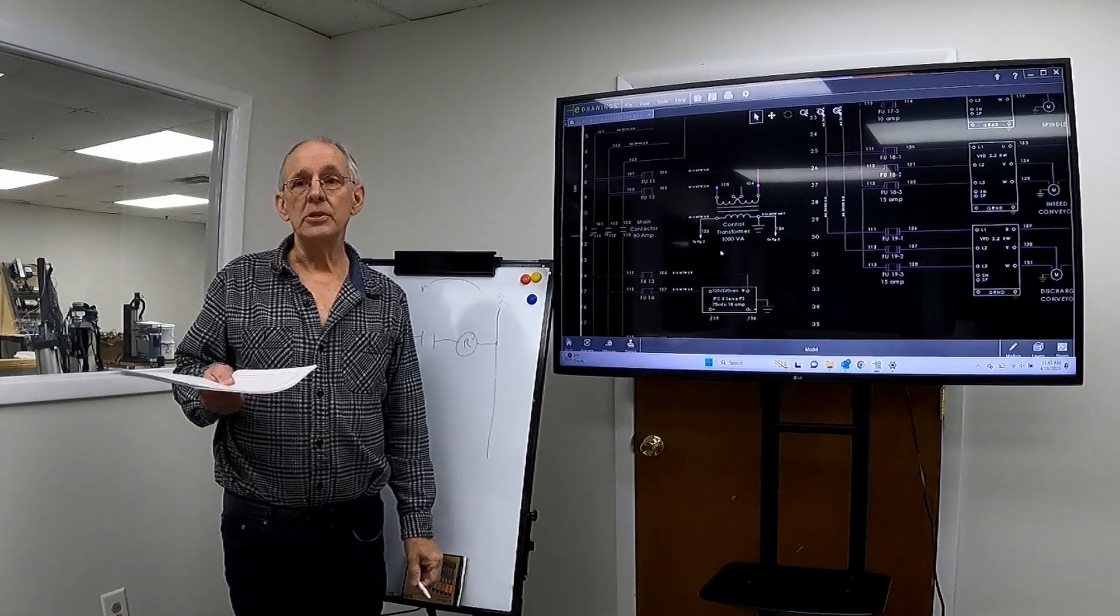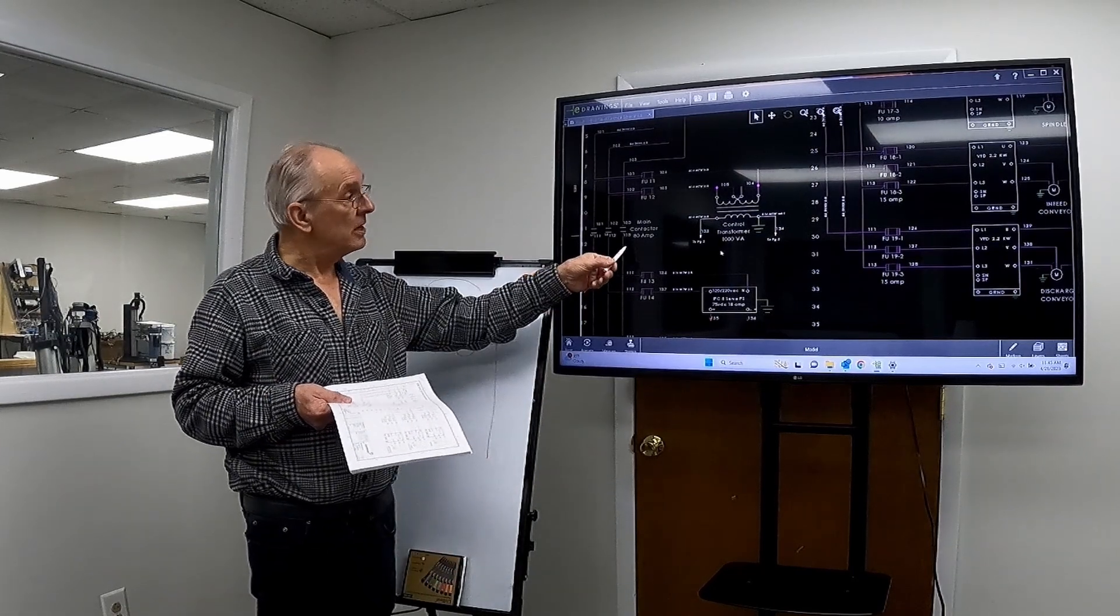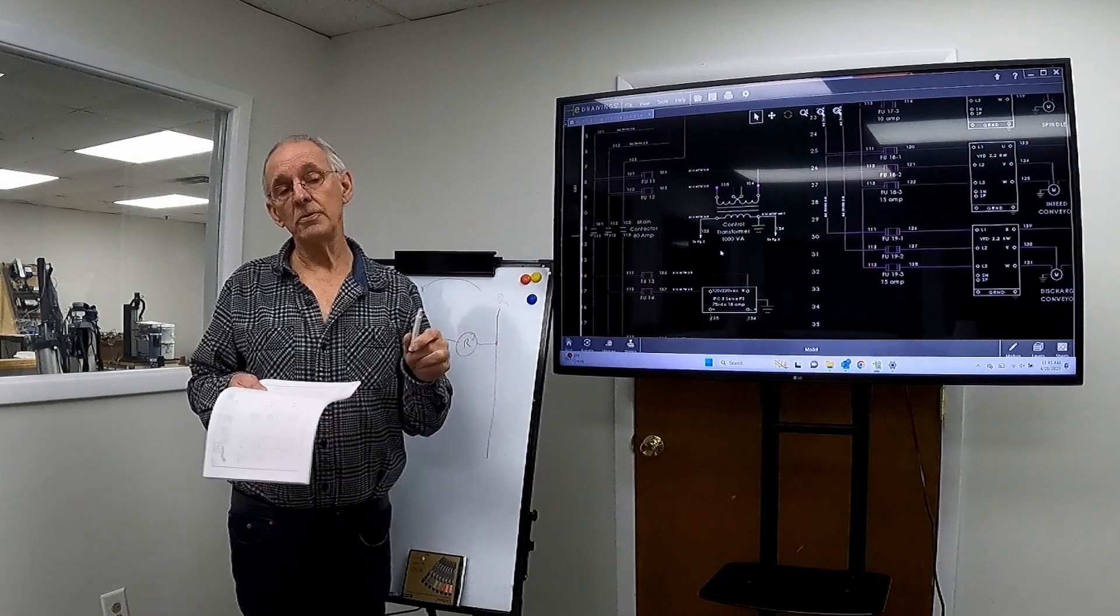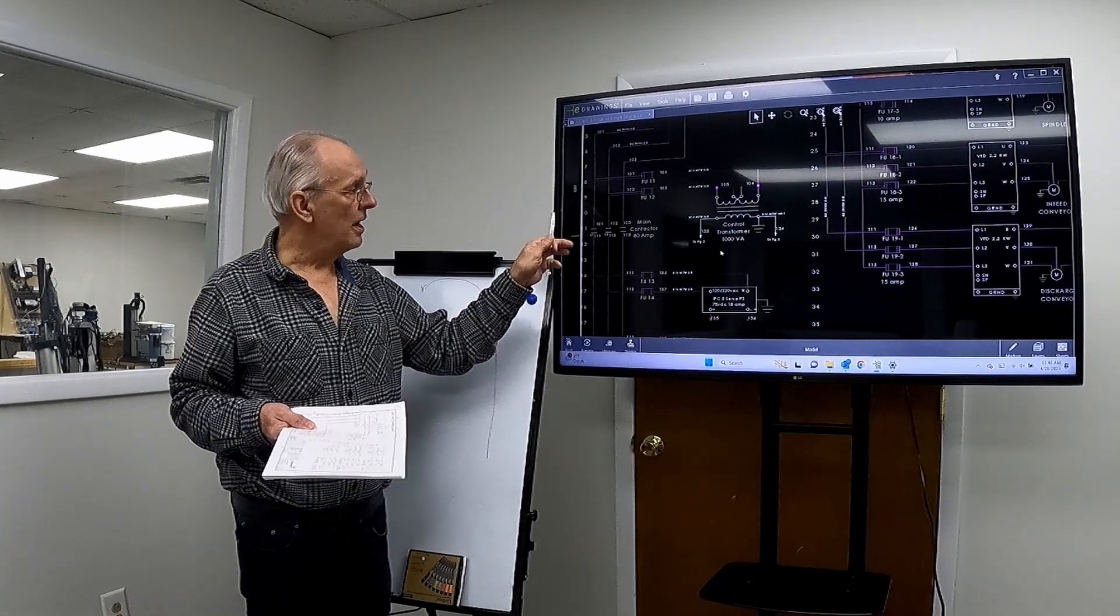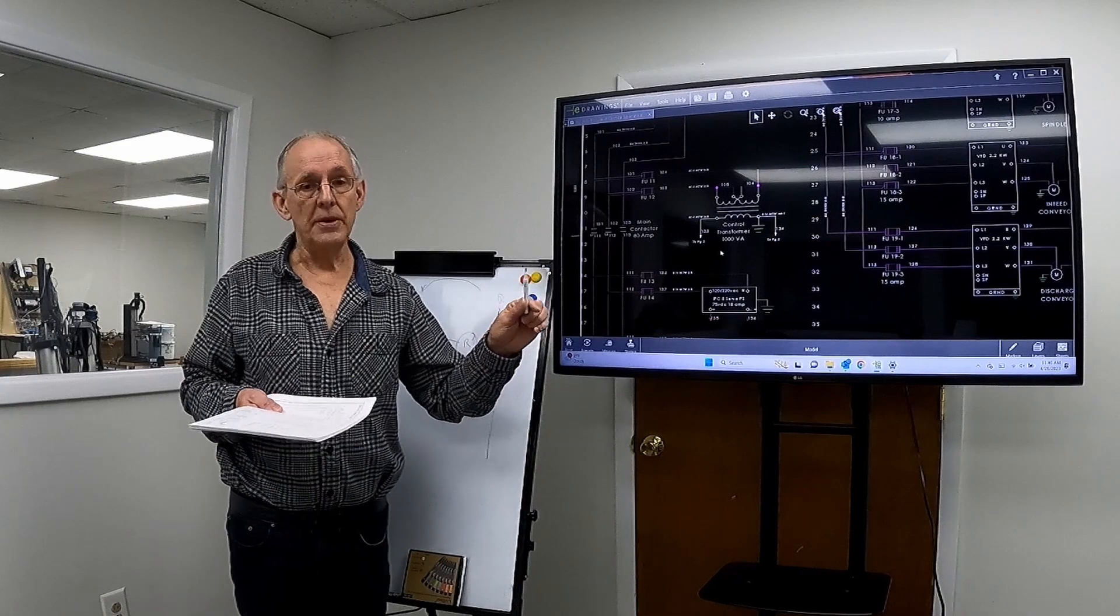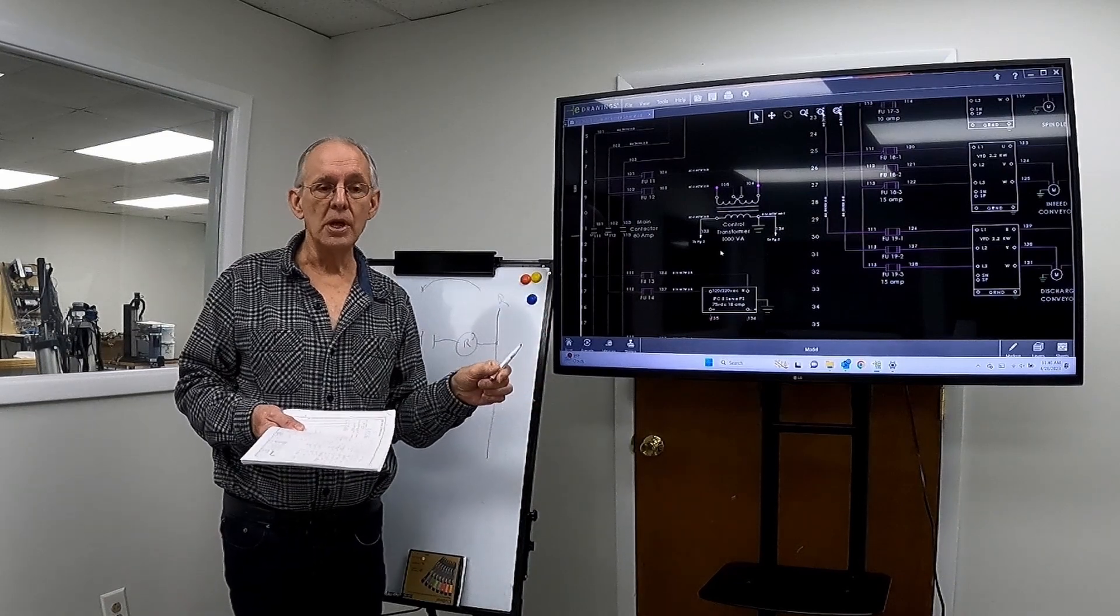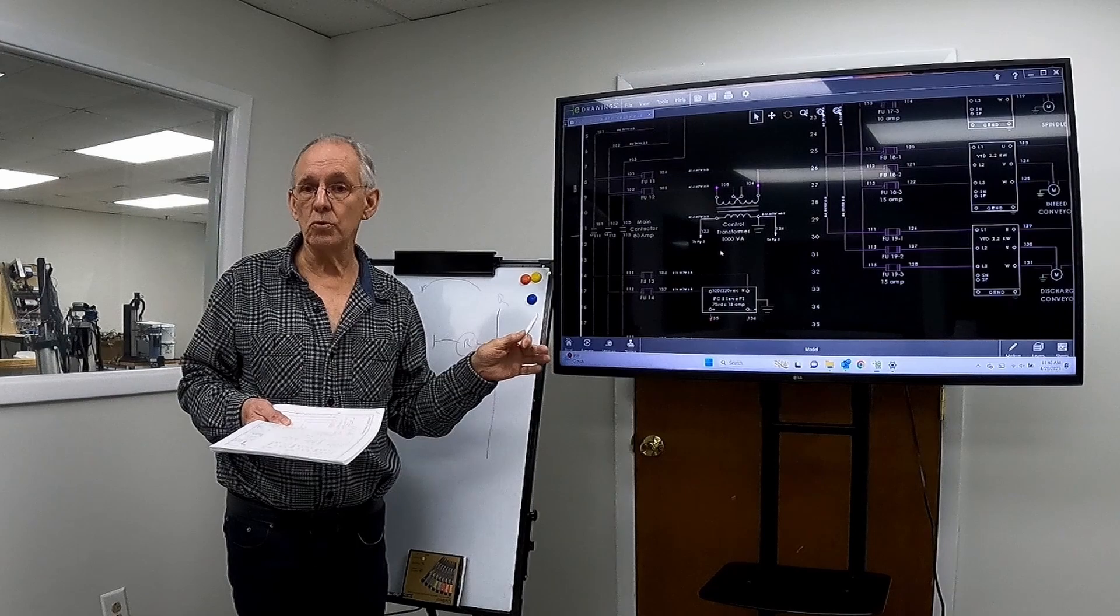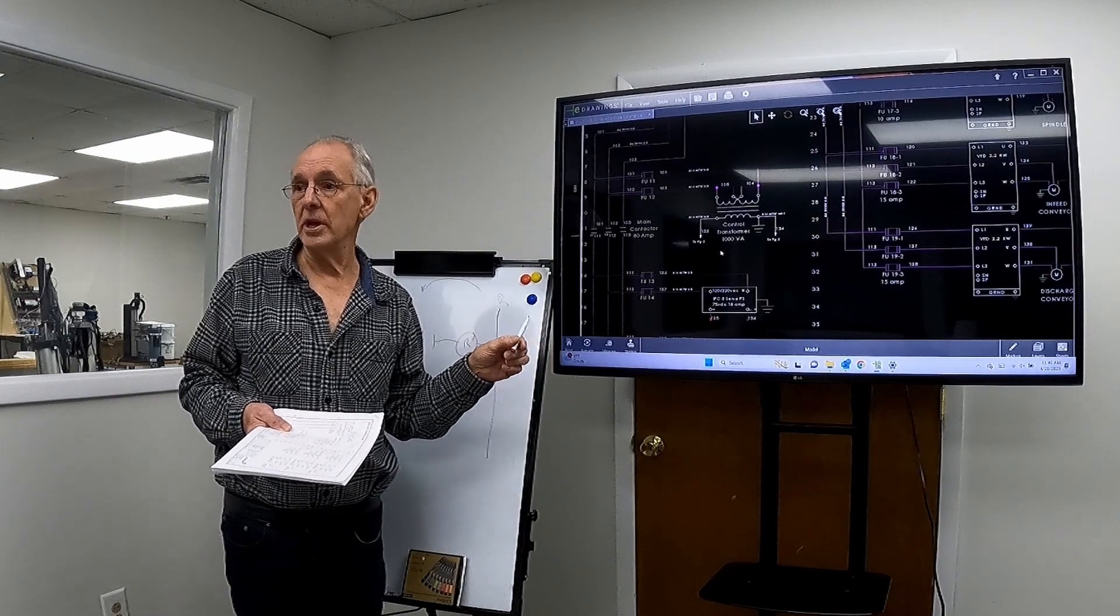That means that the main contactor is what the e-stop controls. So every machine we build has a main contactor, and that main contactor is controlled by the e-stop buttons.